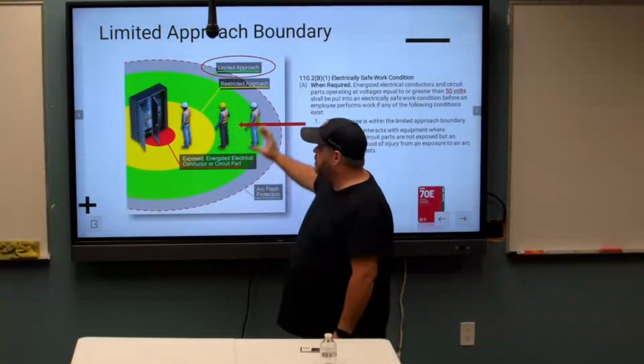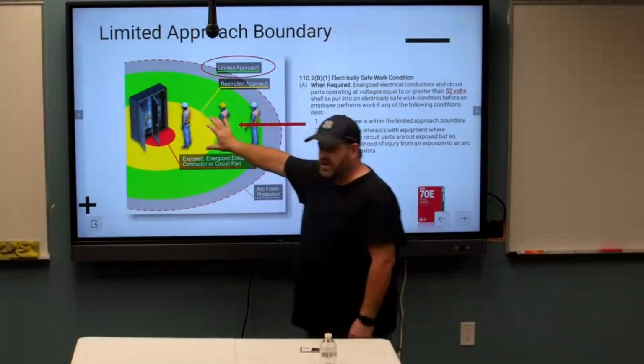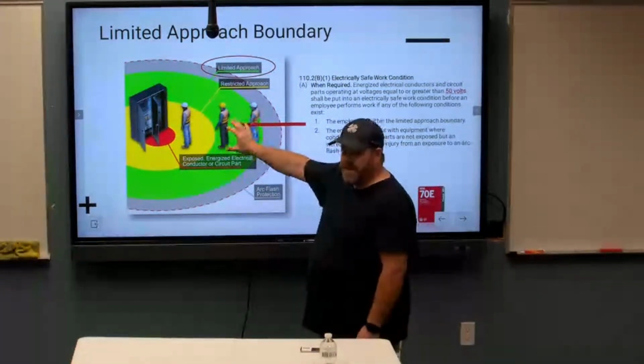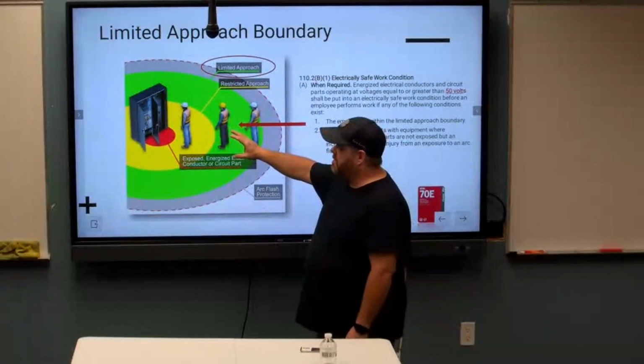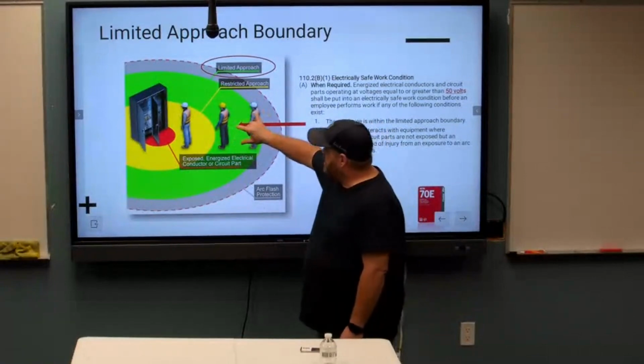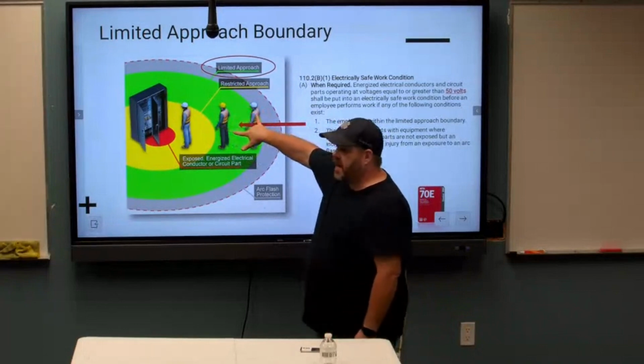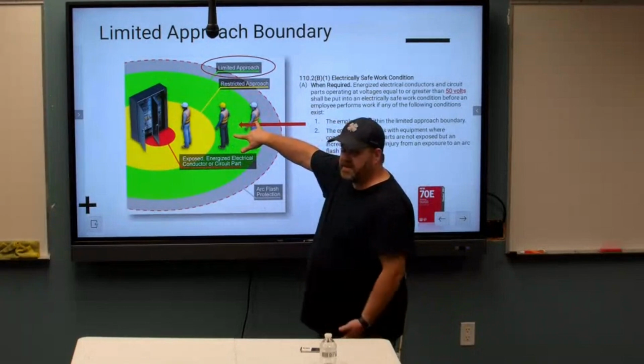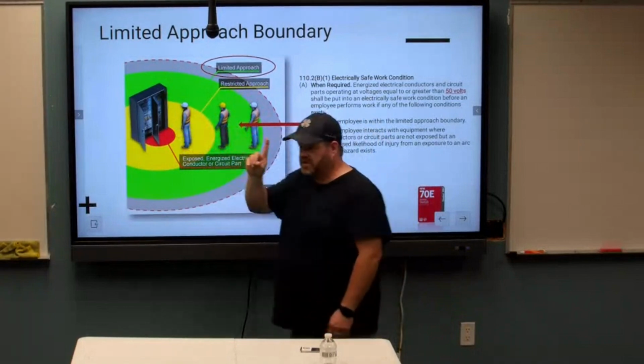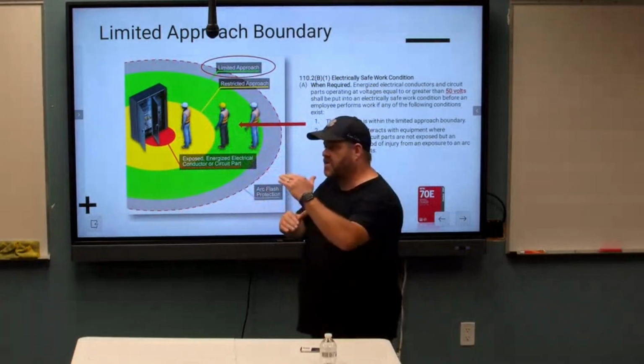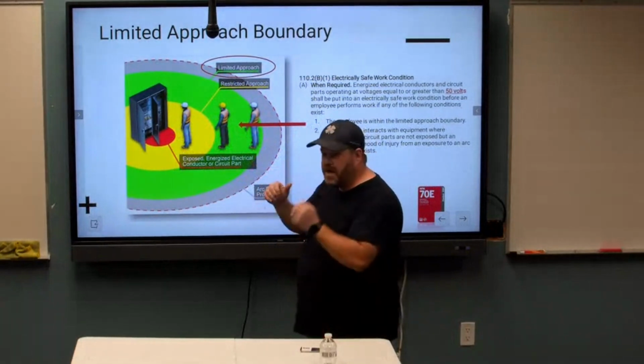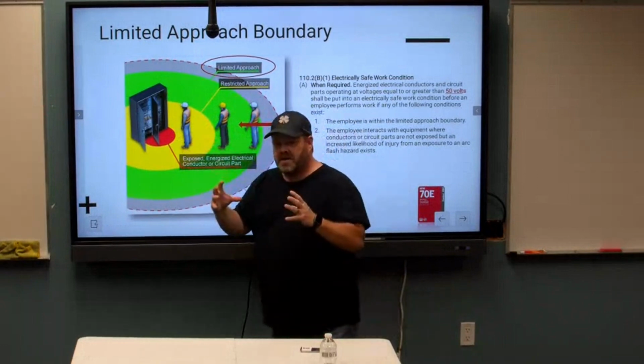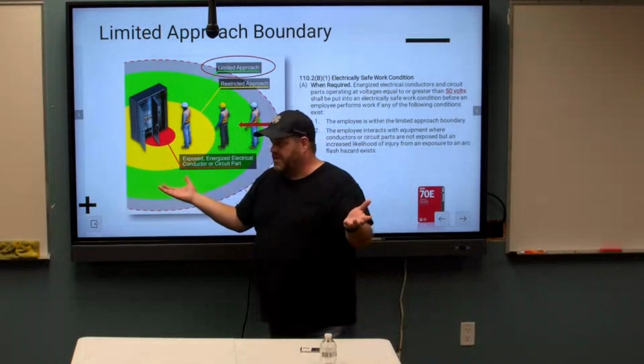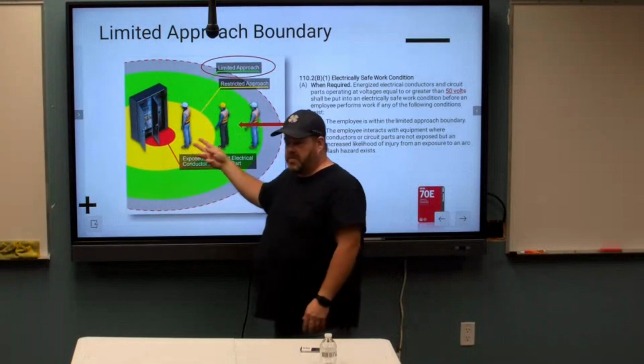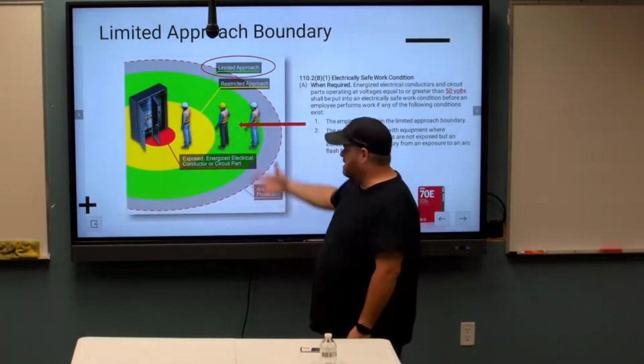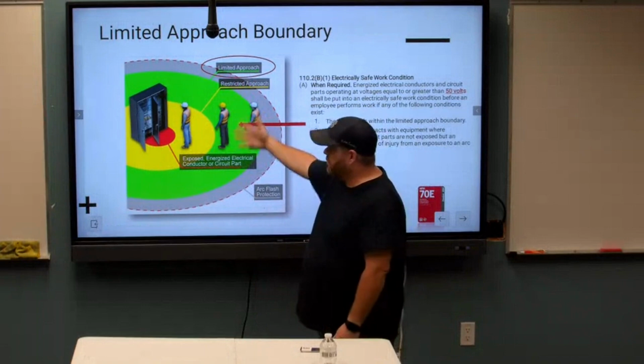Those two tables in the 70E show you how to determine these boundaries. And I'll give you a quick little hint. Up to 400, I think it's up to 750 volts, your limited approach boundary is 3.5 feet for AC systems. Your restricted approach boundary is a foot. But because of our elevation, where we're at in Utah, the 2024 version of the 70E says we have to make the restricted approach boundary a little bigger. So I tell people, double your boundaries. Just make them bigger. Like 2 feet for your restricted approach, okay? And like 7 or 8 feet for your limited approach boundary.